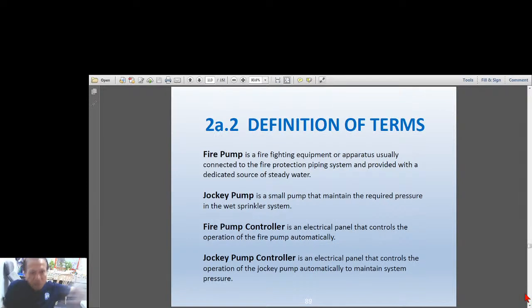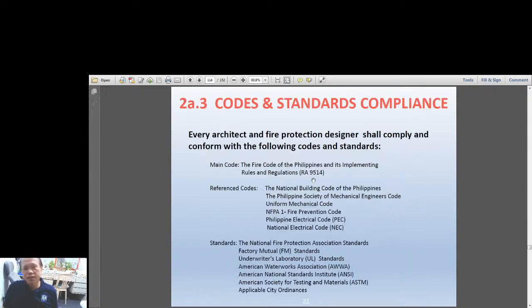Okay, definition of terms: fire pump, then jockey pump. A fire pump is a firefighting equipment or apparatus usually connected to the fire protection piping system, provided with a dedicated source of steady water supply. Then a jockey pump is a small pump, usually running every now and then to maintain the pressure in the hydraulic system. Usually a jockey pump is about 1/10 of the size of the calculated or selected fire pump. So if your fire pump is 50 horsepower, chances are your jockey pump is about 5 horsepower or even less.